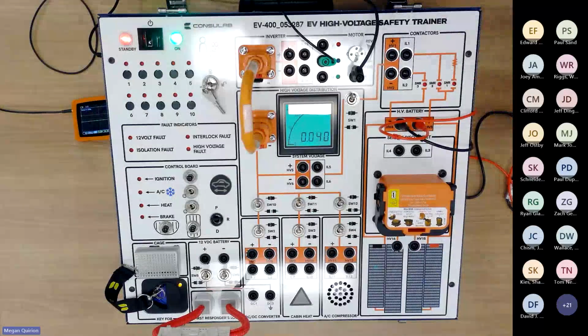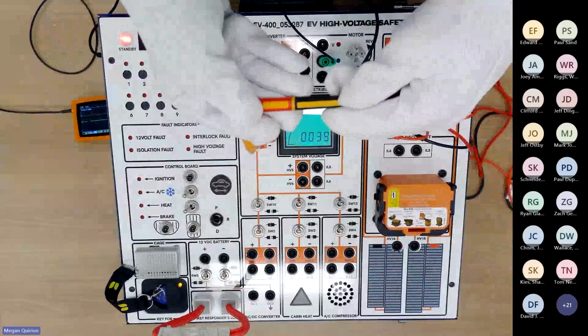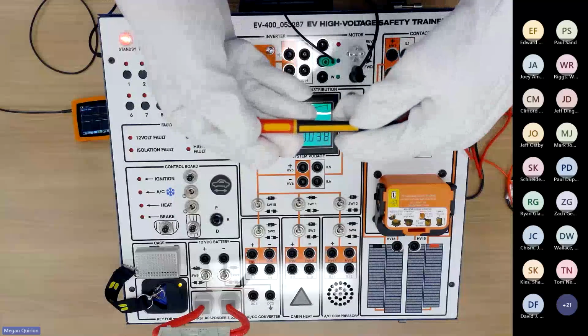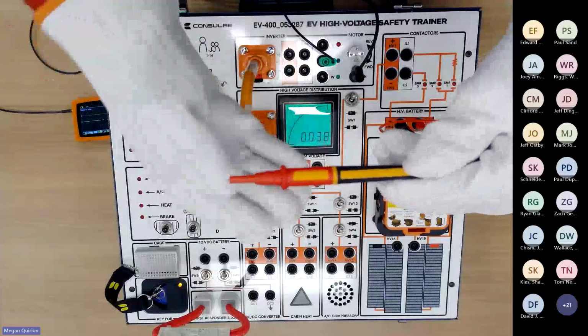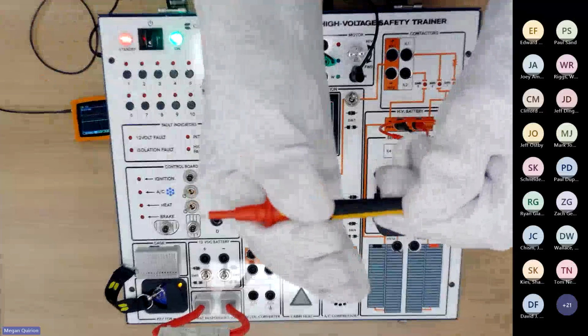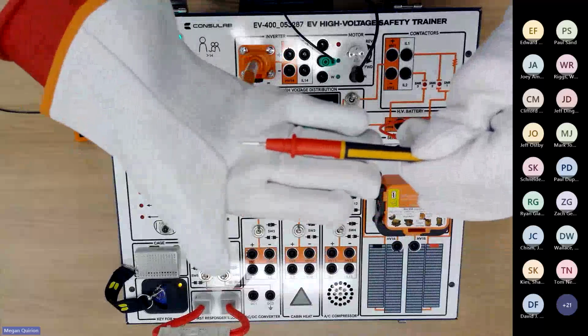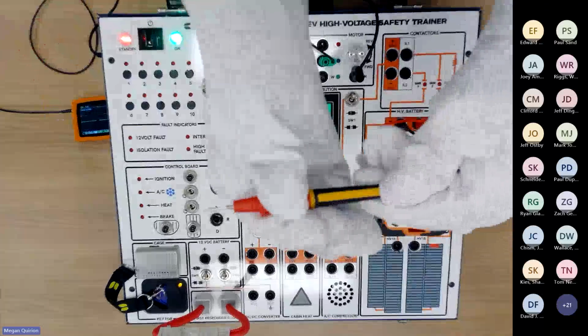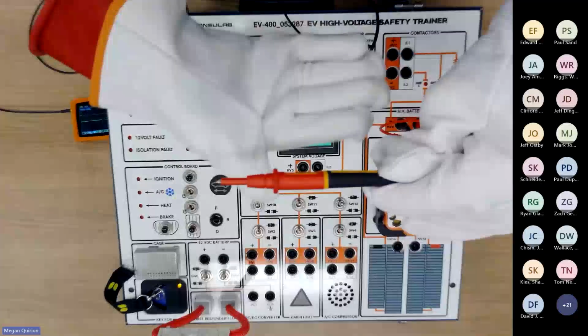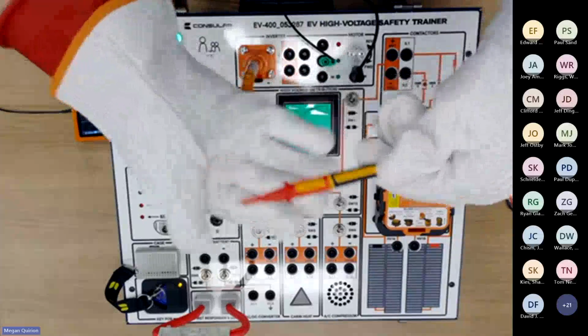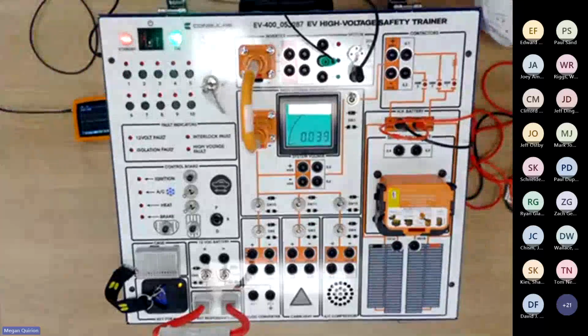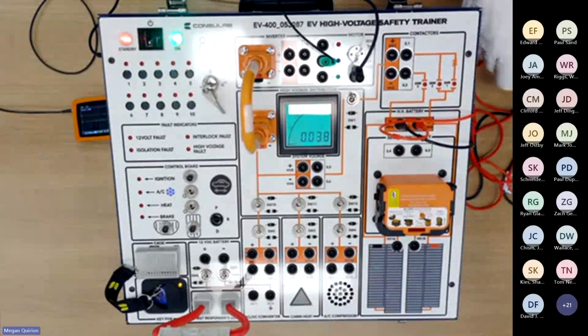We know what students and even technicians are like, losing components and stuff. This is a really cool lead from Fluke, a Cat 3 meter lead that also has a retractable cover. If you're doing low voltage testing and need to get the probe in a bit further, it can retract back to allow that. But if you're going into a high voltage situation requiring that Cat rating, you can extend the cover over the end, exposing about 4 millimeters of the probe, which still retains its Cat rating on that lead.